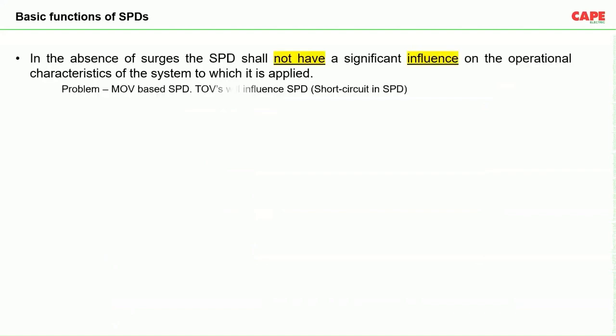SPD has three basic functions. First, in the absence of surges, SPD shall not have any significant influence on the operational characteristics of the system. When voltage is normal and stable, SPD should be completely passive and not create any interference. In MOV-based SPDs, there can be a problem of leakage current, and TOV can also influence the SPD — these will be discussed in future webinars.